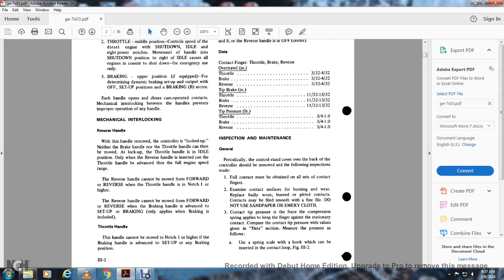Inspection, maintenance, periodic. The control stand cover over the back of the control stand should be removed and the following inspection made. Proper contact must be obtained on all sets of contact fingers. Examine the contact surface for burning and wear. Replace badly worn, burned, or pitted contacts. Contacts may be filed smooth with a fine file. Do not use sandpaper or emery cloth.